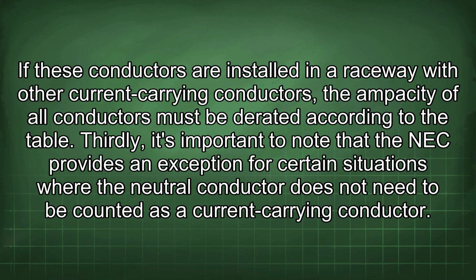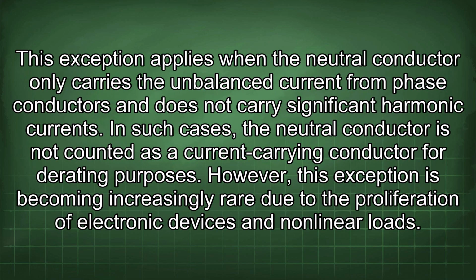according to the table. Thirdly, it's important to note that the NEC provides an exception for certain situations where the neutral conductor does not need to be counted as a current-carrying conductor. This exception applies when the neutral conductor only carries the unbalanced current from phase conductors and does not carry significant harmonic currents. In such cases, the neutral conductor is not counted as a current-carrying conductor for derating purposes. However, this exception is becoming increasingly rare due to the proliferation of electronic devices and nonlinear loads.